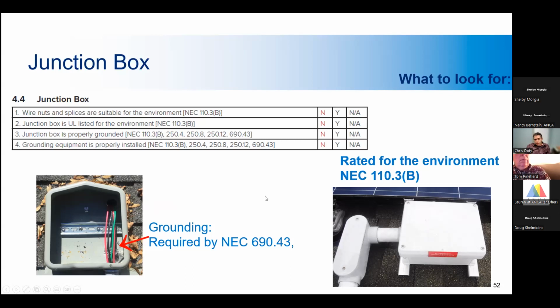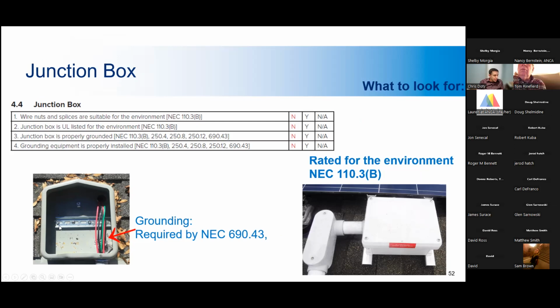One thing to keep in mind is a conductive enclosure. This is a metal enclosure. It is considered likely to become energized because it's a conductive enclosure. So this would actually fail the inspection, because it's a metal enclosure and it should be properly bonded to the grounding system, which it's not. The ground wire, the green wire here, just runs right through and is not connected or attached to the junction box. So the junction box is not grounded.